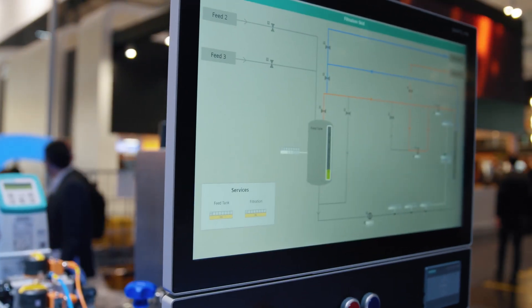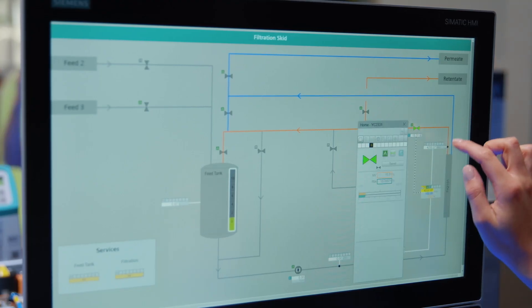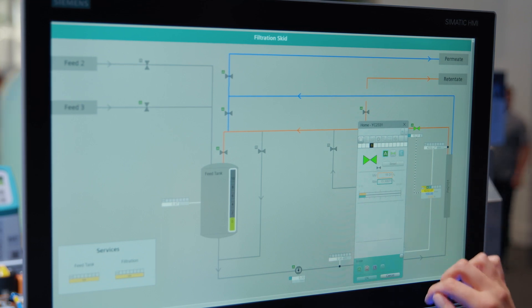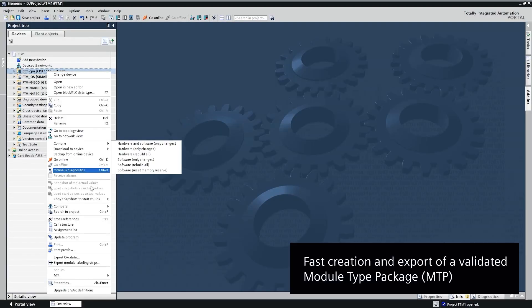The automation engineering of the individual modules is done in the TIA Portal using an S7-1500 controller and the HMI system Simatic WinCC Unified. We use the Simatic process function library, which natively implements the MTP standard. To enable object-based engineering, we provide standard function blocks and block icons for monitoring and control. This saves validation time.